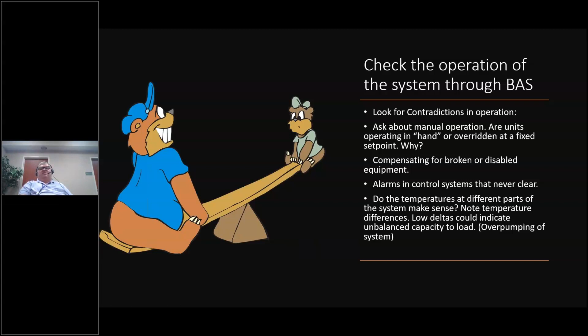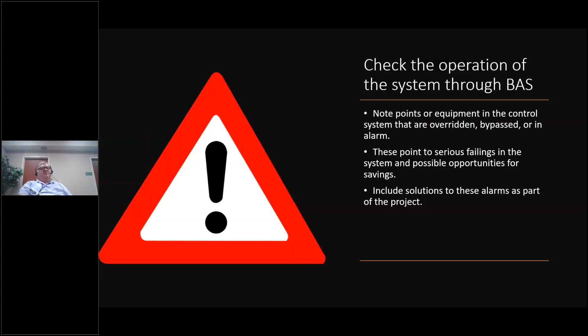The alarms are key. Points or equipment in the control system that are overridden, bypassed, or in alarm point to serious failings in the system and possible opportunities for savings, but you have to address these. Include the solutions to these alarms as part of the project. You want to clear these things off if you can, or at least it gives you an indication that something's not working correctly. And your ECMs, your solutions, could address and resolve these issues.